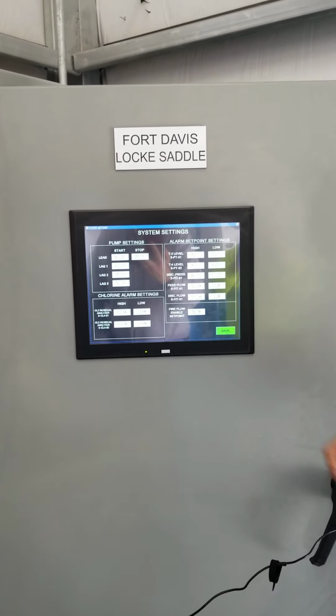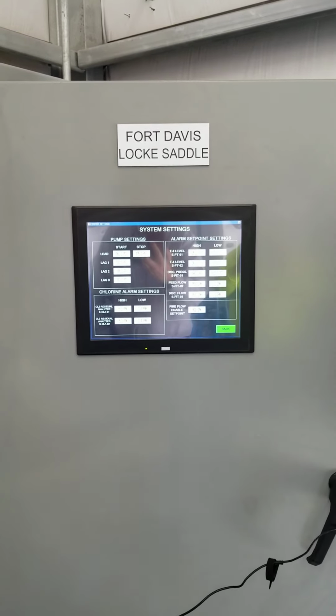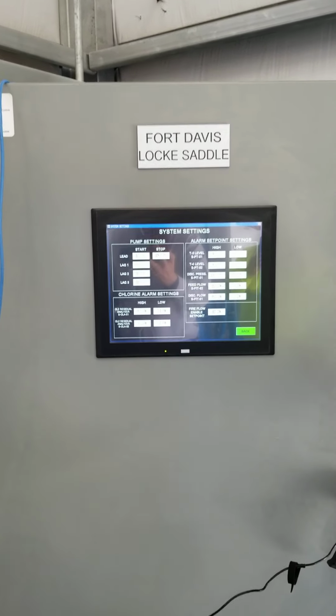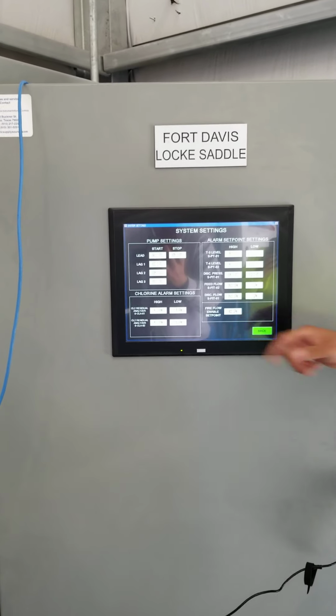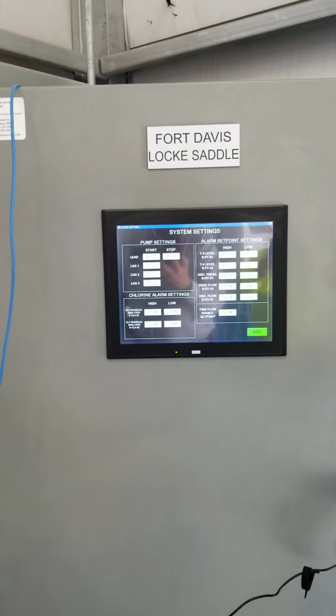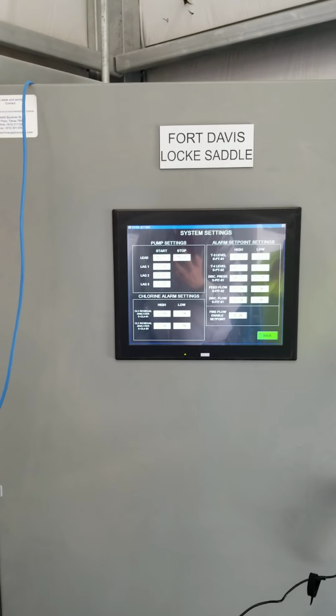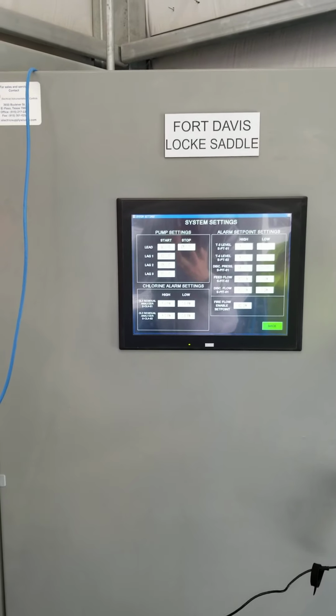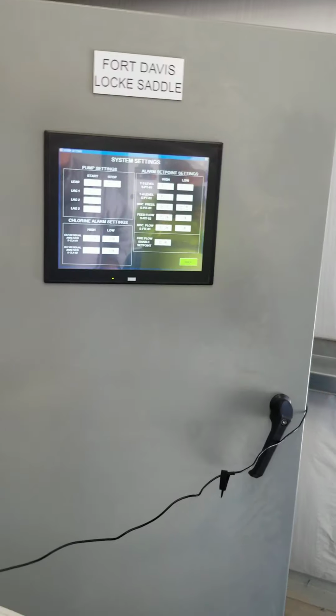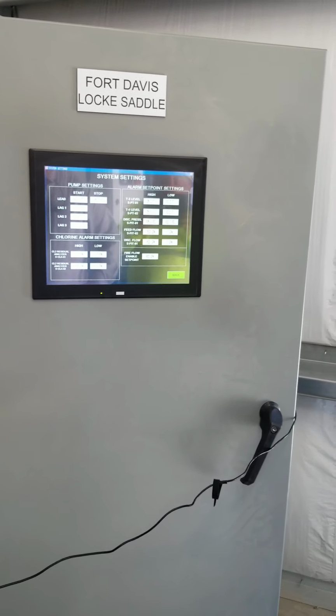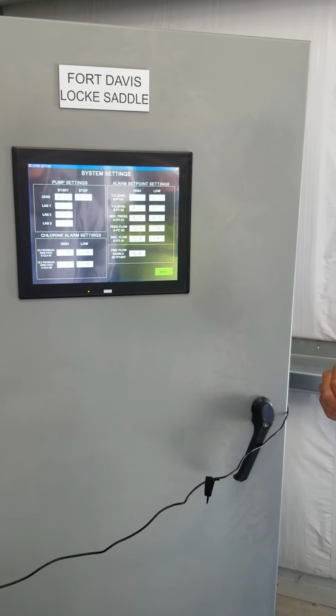This is very important also. That will trigger your fire enable. In case of a fire, what GPM you want it to trigger. If you want it to be lower, you can put it at 500 GPM, and as soon as it sees 500 GPM, it's going to trigger all the pumps, or as many pumps to turn on at the same time. Well, not at the same time. It's going to stagger them at least a second for each to turn on. But that will trigger for emergency, where you need to put out a fire.